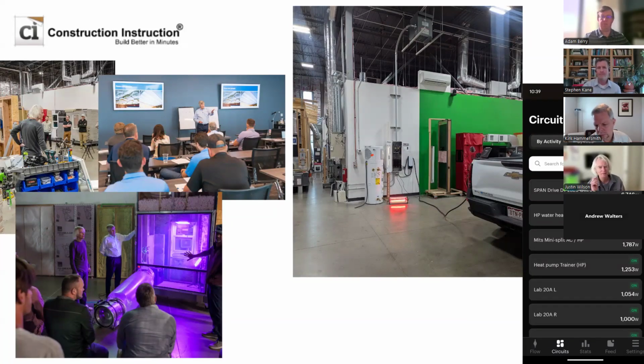If we're right sizing things in the house, mechanical systems, heating, cooling, hot water, lights and appliance loads that are controlled in the building, and having a pretty good understanding of them, it's looking at the areas that require, in my opinion, extra breaker space in the field that we work in. Okay, we have a heat pump. We have a cold climate heat pump. In Denver, if you have a cold climate heat pump and you pick the right one that's complementing the right enclosure, so the heating and cooling loads are relatively balanced based on the insulation levels, air sealing, and windows that you've chosen, does the heat pump need backup heat? This is where I'm going with this. Meaning, do I really need with a heat pump a 40 amp breaker that's emergency or backup heat on a system that's designed and manufactured to deliver 100% of its heat well below 5 degrees Fahrenheit, which is crossing the design temperature for most of the Front Range of Colorado?